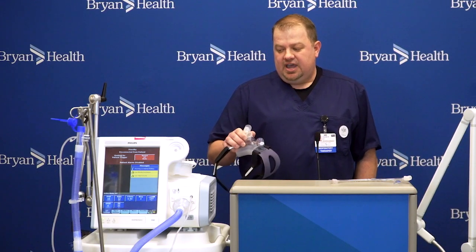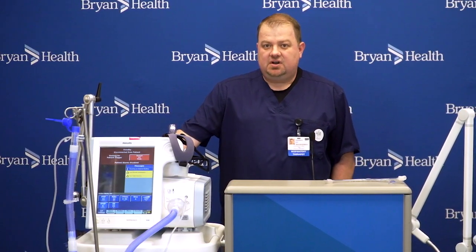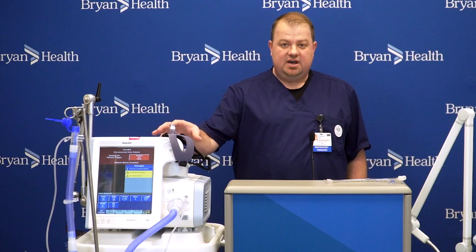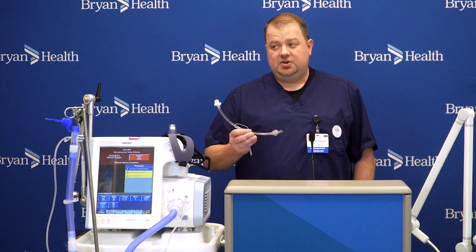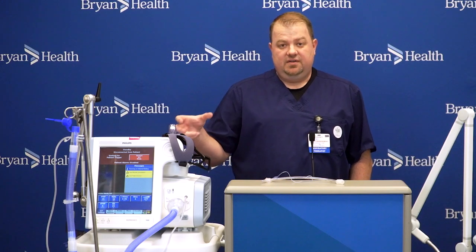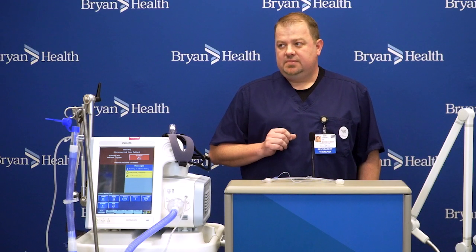As far as the software built into our V60 machines, once we have moved on from a mask and intubated the patient with an endotracheal tube, we have to tell the software that there's less of a leak and there are going to be tighter pressures, and then change our alarms so that we're taking care of the patient properly and effectively.